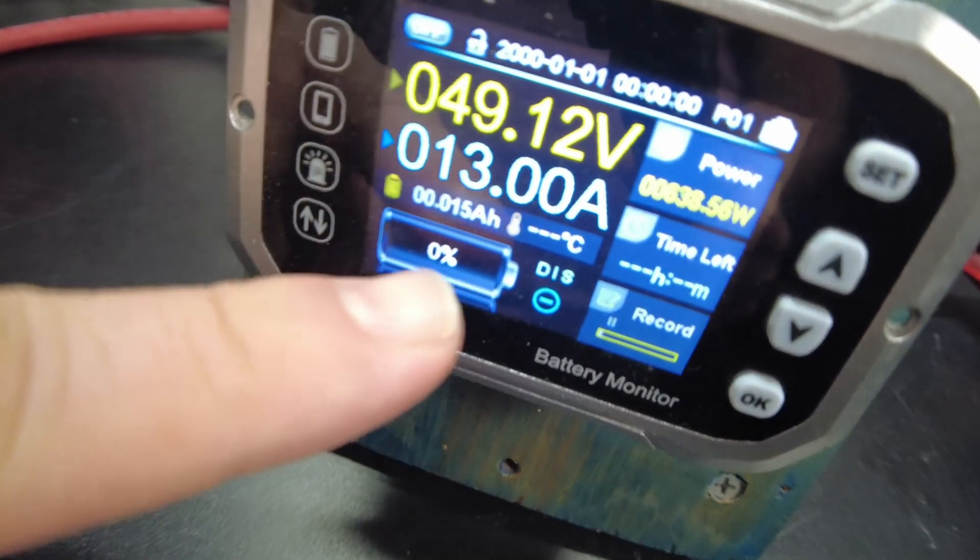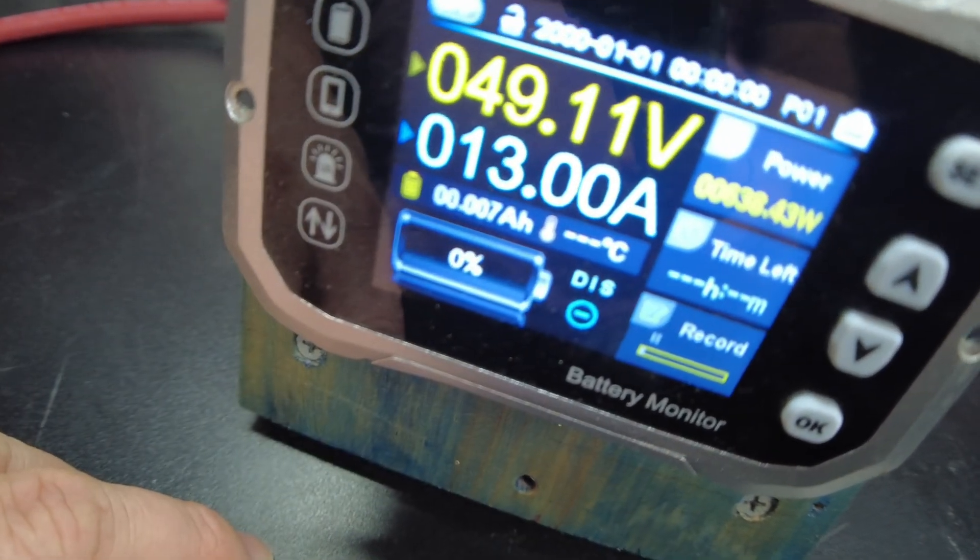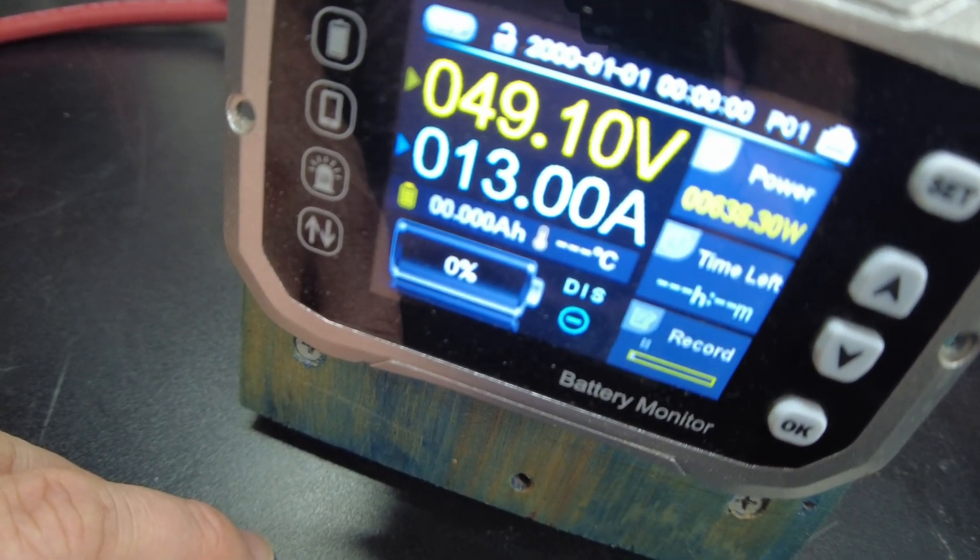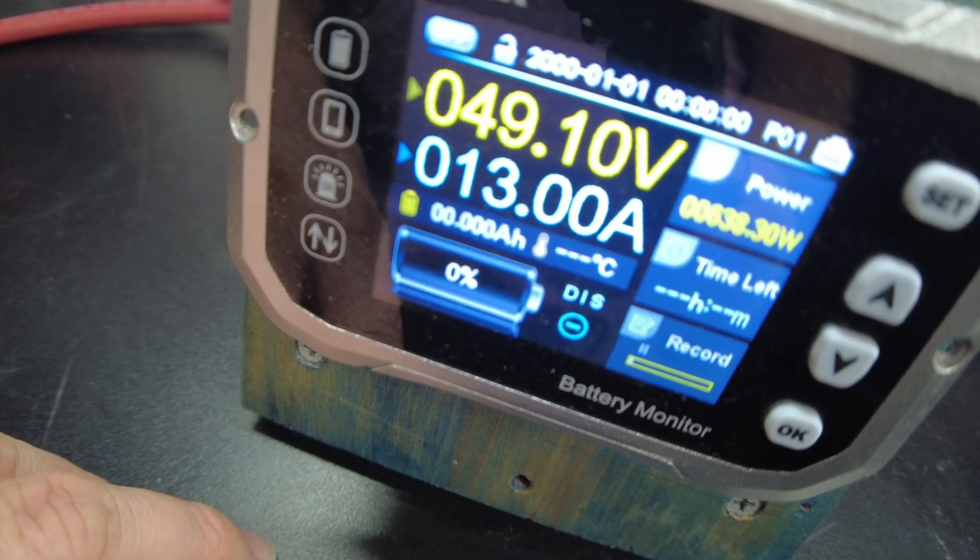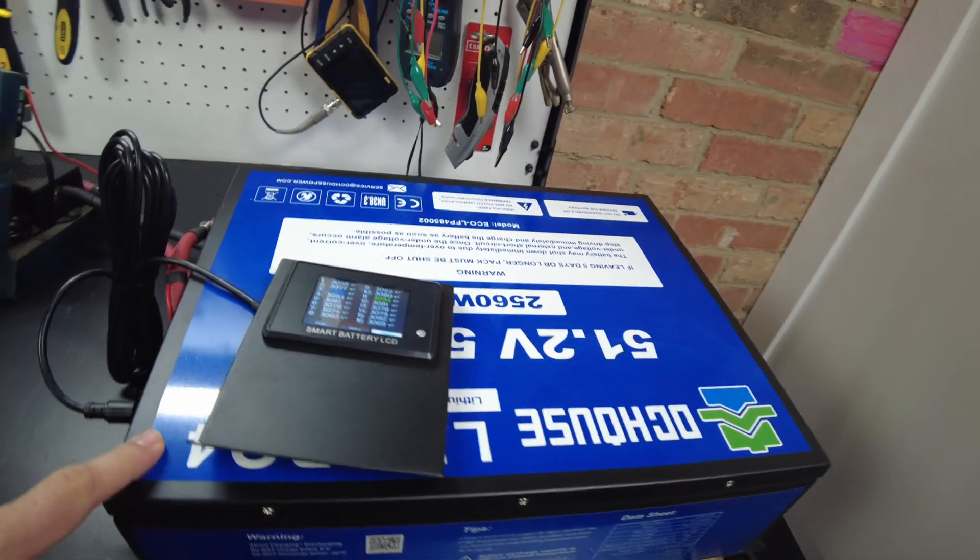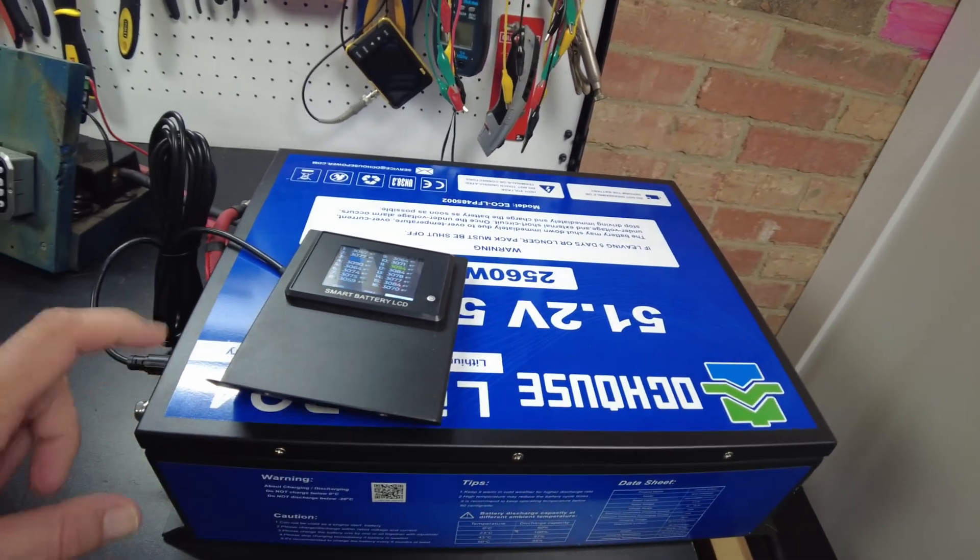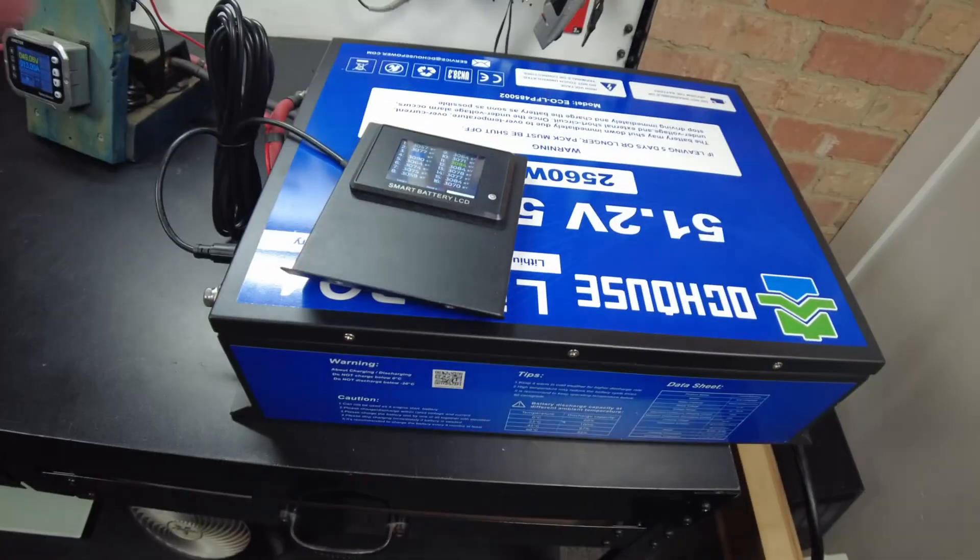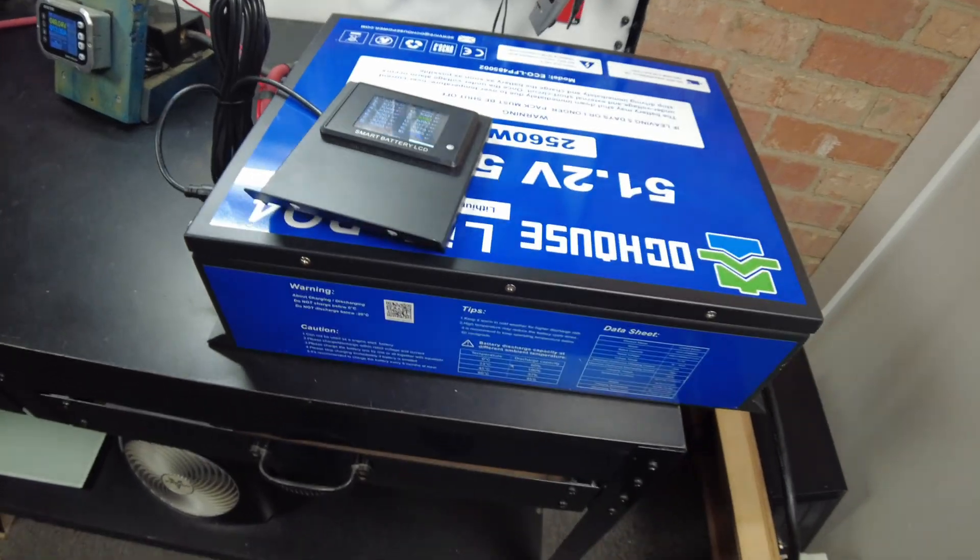Alright, so here we go. We're about to hit full capacity. Bam! We have discharged a full 50 amp hours, which is the rated capacity of this battery, so it definitely does pass the capacity test. Very good.